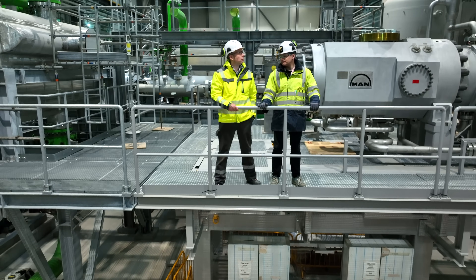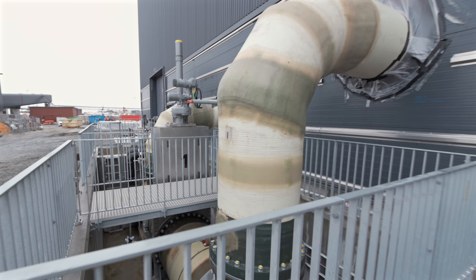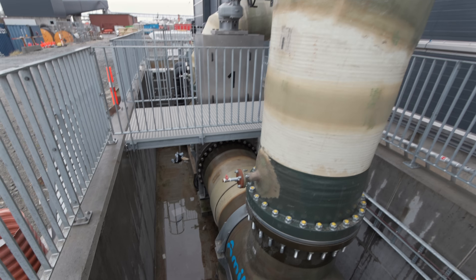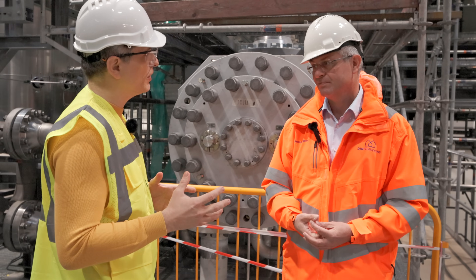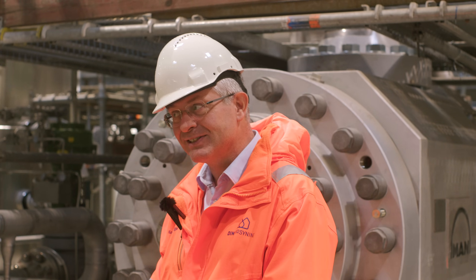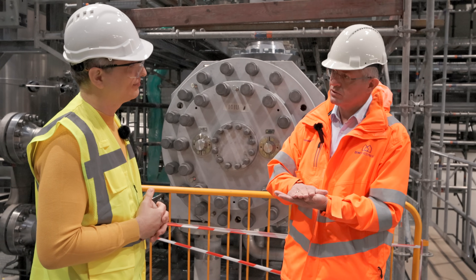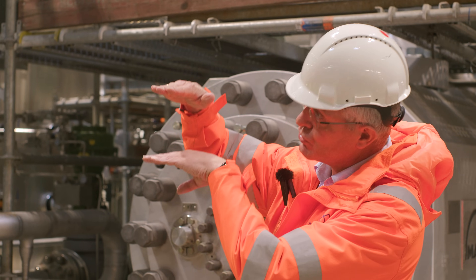So the first big difference, besides the size, is the heat source: not air but seawater. It could have been air, but the giant fans and evaporator heat exchangers would need to be two or three football courts in size. Seawater is a much more interesting and stable source of heat. Does it also provide an advantage because it doesn't go below zero as air sometimes does? Well, water can in principle freeze, but the seawater here rarely has ice. We take the water very close to the bottom of the harbour — if there's freezing, ice goes up, not down.